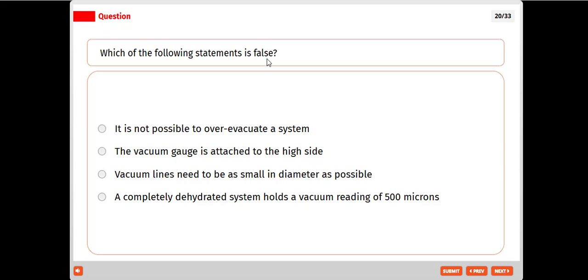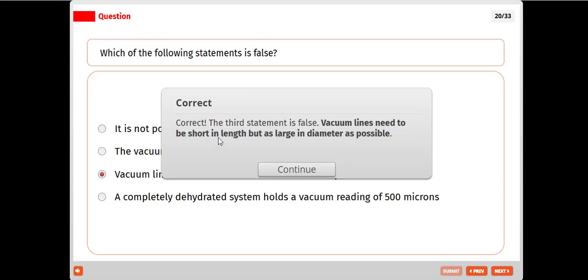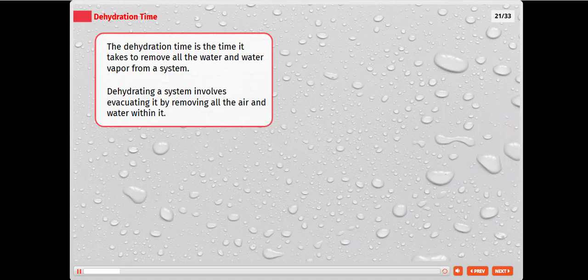Which of the following statements is false? It is not possible to over-evacuate a system. No, it's possible. A vacuum gauge is attached to the high side. Okay. Yeah. Vacuum line needs to be as small in diameter as possible. No. A completely dehydrated system holds a vacuum reading. Well, I think this is correct. Vacuum lines need to be short in length but large in diameter as possible. Dehydration time is the time it takes to remove all water and water vapor from a system.